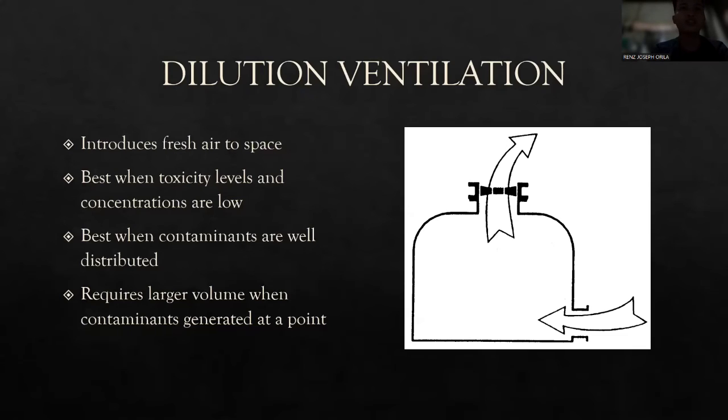Dilution ventilation introduces fresh air to space. It is best when toxicity levels and concentrations are low, and best when contaminants are well distributed, and it requires larger volume when contaminants are generated at a point.